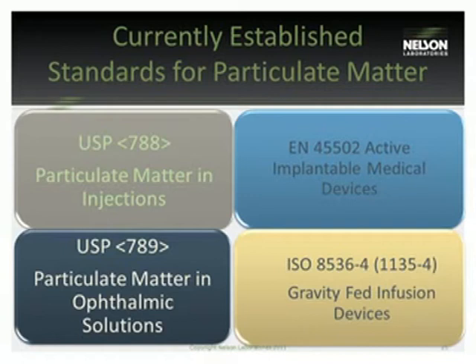USP 788 is the most common for particulate matter in injections and parenteral infusions. Anything that's injected into the bloodstream or tissue usually has to pass 788. There are very specific limits for both small volume injectables and then large volume, which are things such as IV bags and larger volume fluids. 789 is specific to ophthalmic solutions. It's a little bit more liberal than 788 because it's going in your eyes rather than in your bloodstream. And while it doesn't sound like you'd want too many particulates in your eyes, it's, I suppose, not quite as bad to have them in your eyes as it is in your blood. So that's a little more liberal than 788.